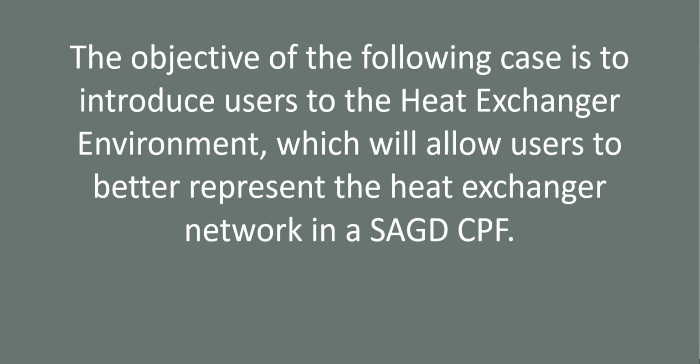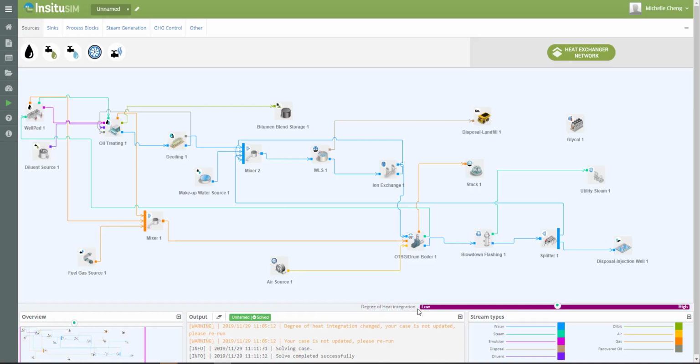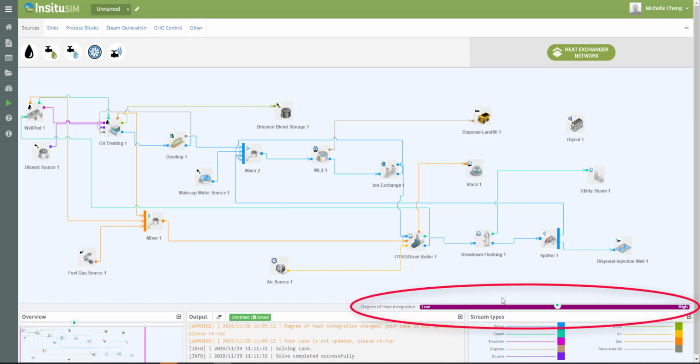By incorporating heat integration through heat exchangers, a process can be optimized to recover waste heat within the facility and utilize it to increase the temperature of cold streams when needed and vice versa. Currently, BFW temperature is estimated using heuristics from concepts such as the pinch analysis, which reduces the overall minimum approach temperature to improve energy efficiency. The degree of heat integration can be improved by moving the slider to the right to increase heat recovery.